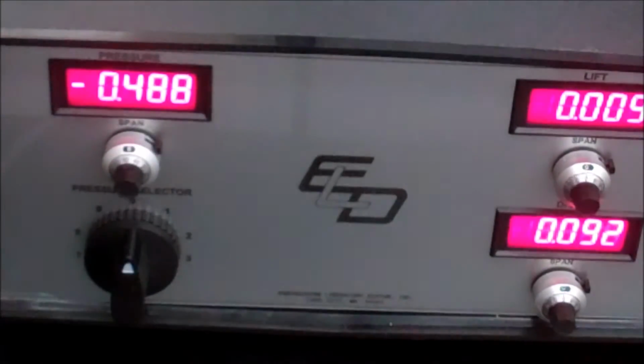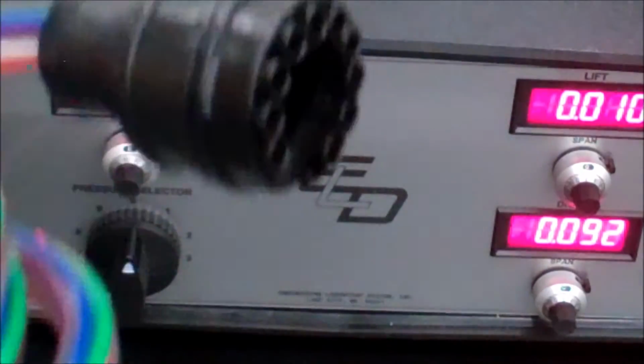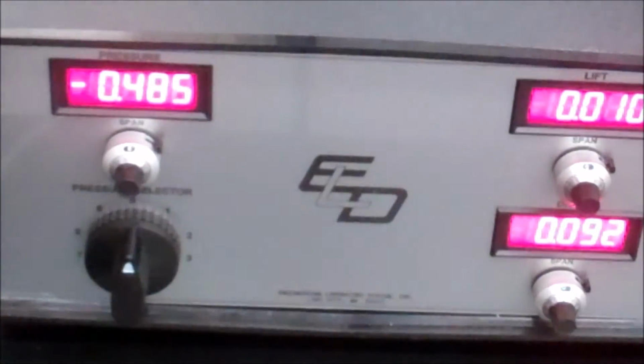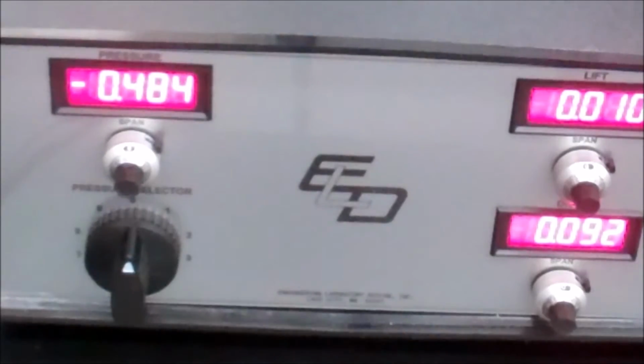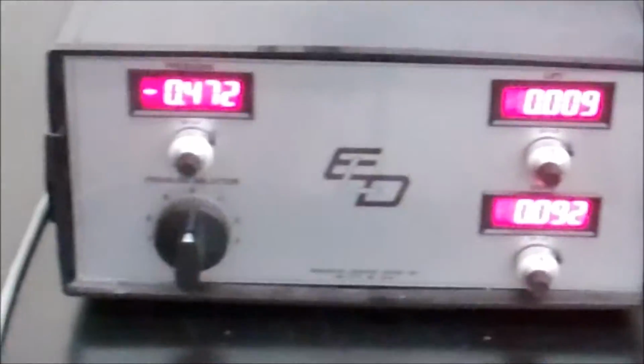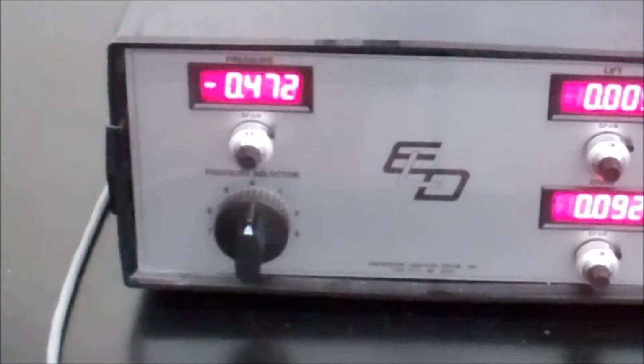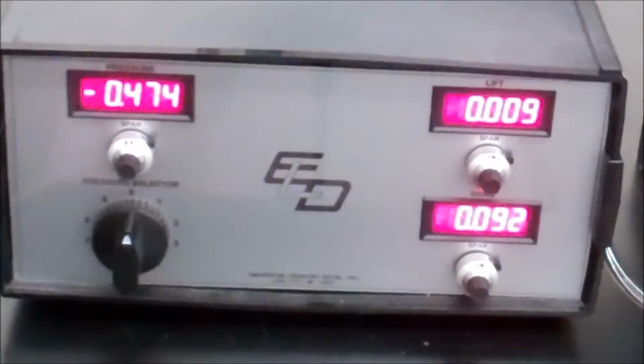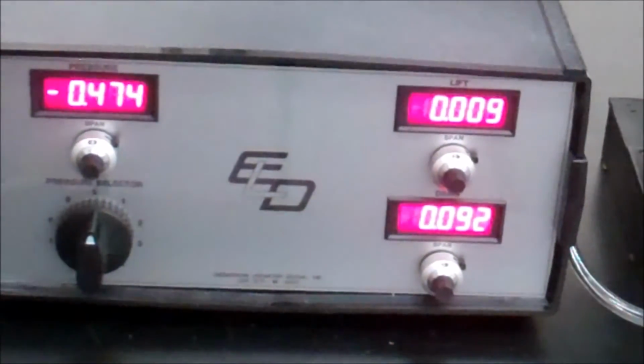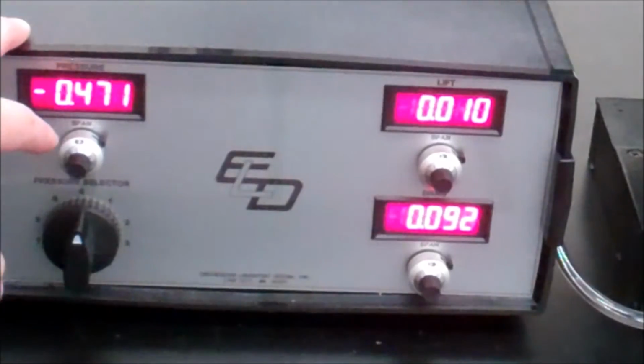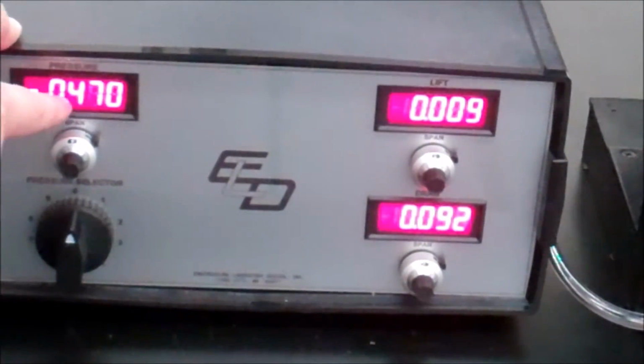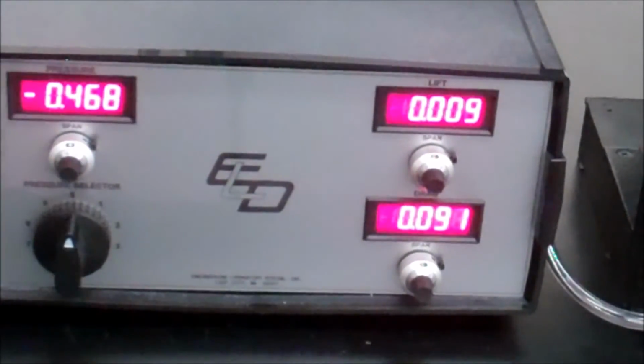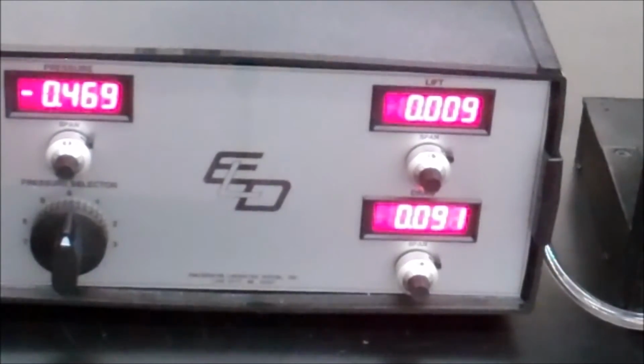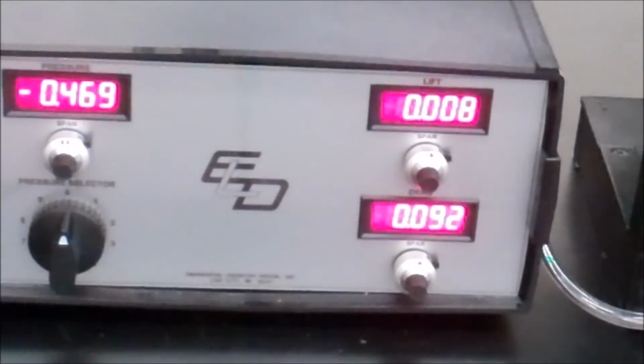Now if there's nothing connected to these lines or to the system itself, and you switch it to 1, 2, 3, 4, 5, 6, 7, 8, 9, then you're just going to get a 0 pressure. So you're going to want to adjust that to make the amplification. Based on your amplification, you adjust the set screw that I just showed you, using a flathead screwdriver, and you adjust it to 0. Now it is kind of finicky, but you can get it to set to 0.